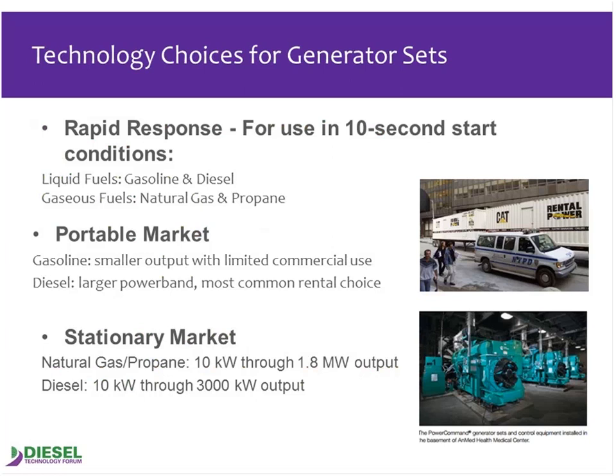For generators, the characteristics we look at to evaluate those systems start with rapid response, for situations where a quick start is needed. A great example would be a hospital setting where power may go out from the grid, and emergency systems in intensive care units, operating rooms, and other main electrical circuits need immediate power. These situations require a 10-second response time as mandated by health and safety codes, and both diesel and natural gas can provide that. Gasoline can also be used in some of those settings.